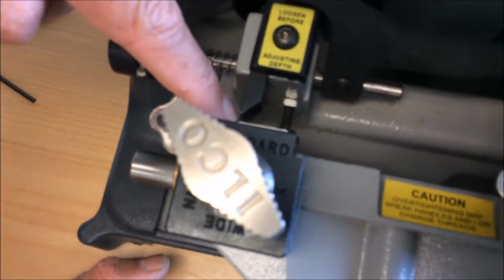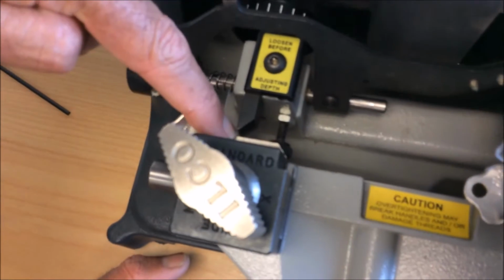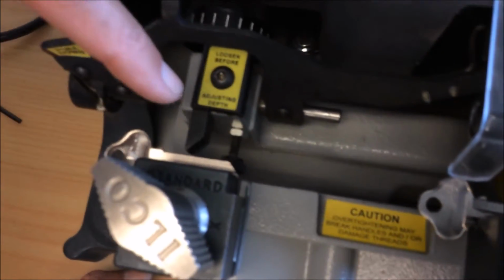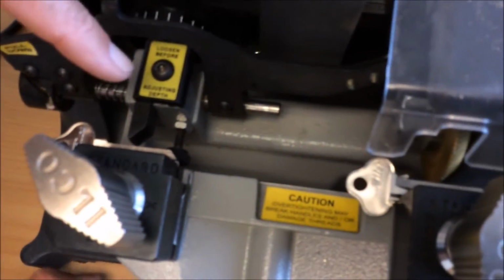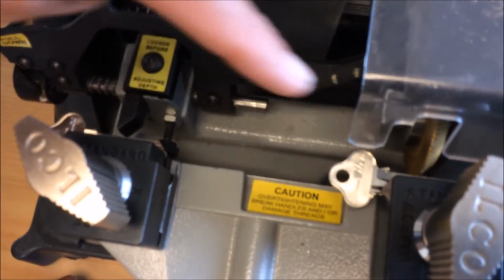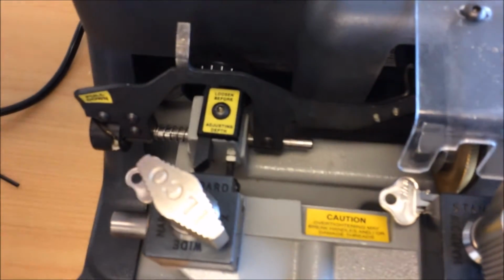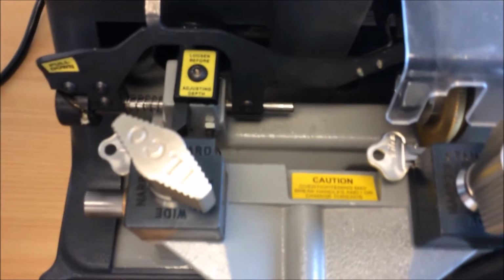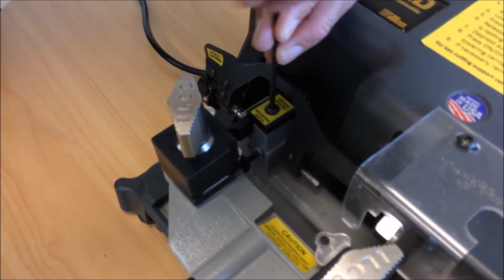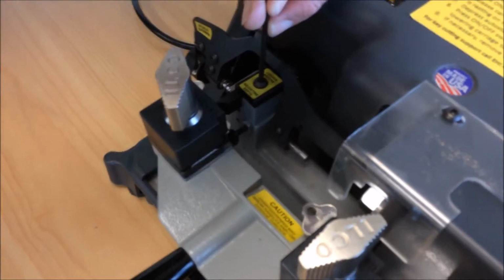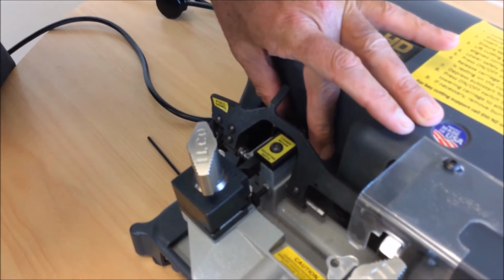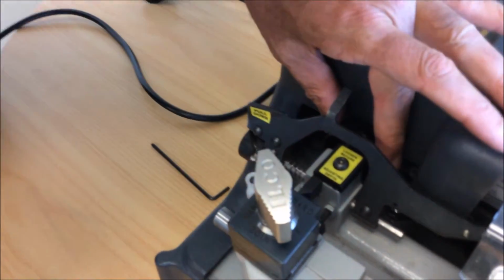That sort of gap, as I mentioned earlier, does indicate that it is out of alignment and needs some adjustment. Equally, you could have the gap on the other side. So we could have no gap here, but we could have a gap on the cutter. Either way, it indicates that you need some adjustment. So the first thing we do, loosen up with an Allen key here. Using an Allen key, we just loosen that a little bit. All that Allen key does is it just locks this adjustment knob, makes it unable to turn.